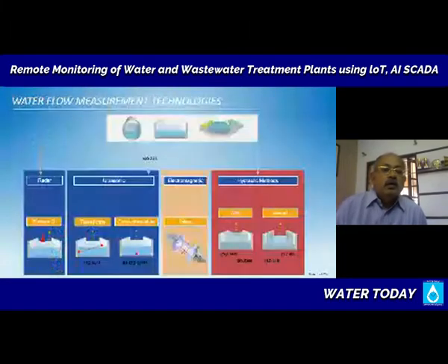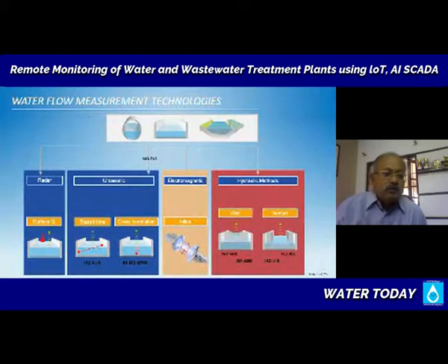Now, of course, you can also measure the velocity of a flow based on some embedded particles. If it is raw water and you have some sand or particles in the water, then these suspended particles can be tracked. You look at the position and you look at the same particle after so many milliseconds, how much it has traveled. And thus, the instrument works out the velocity for you. The international standard ISO 18769 governs this kind of Doppler, or what we call cross-correlation measurement. We can look a bit more into it as we move forward. So these are ultrasonic measurement solutions.